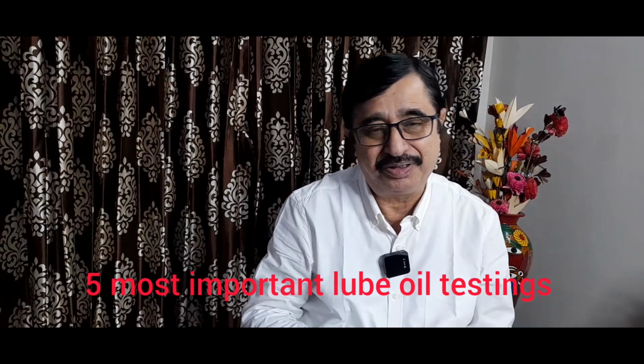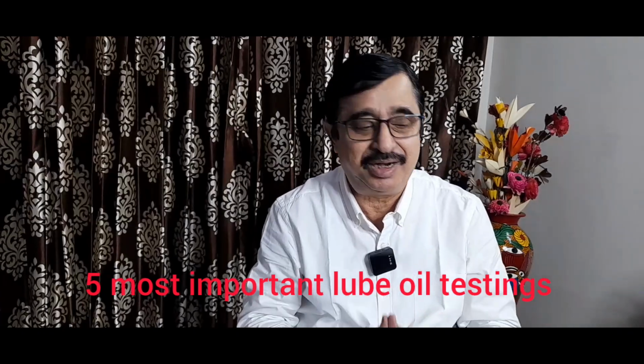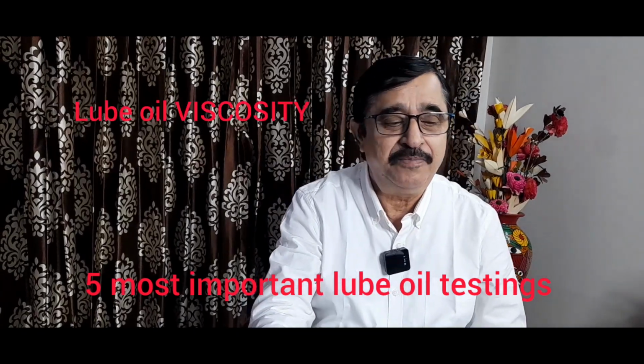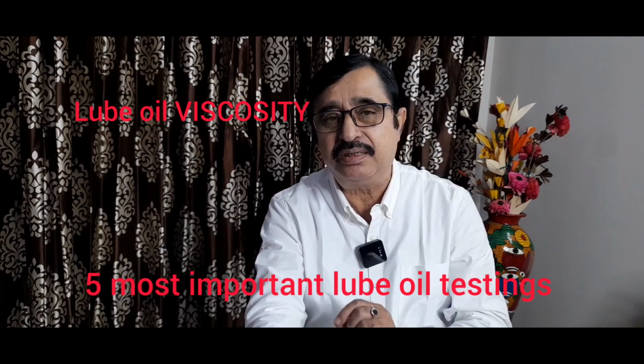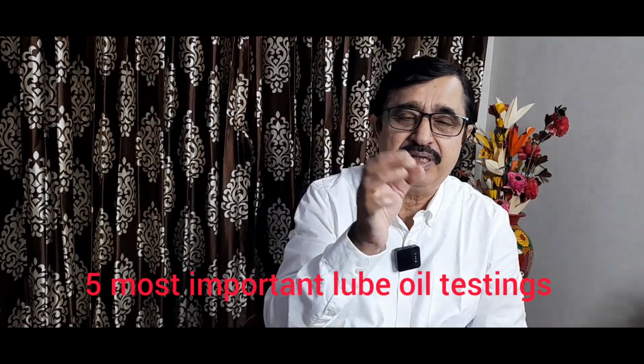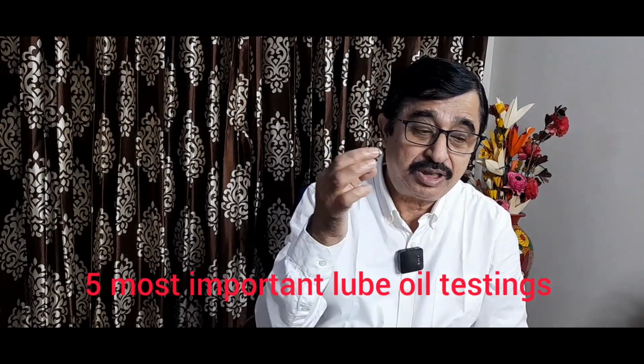Let us start the 5 analyses. What are the 5 analyses? So the first analysis is that lube oil viscosity analysis must be done on a very regular basis. Say I am talking about a monthly basis, right?